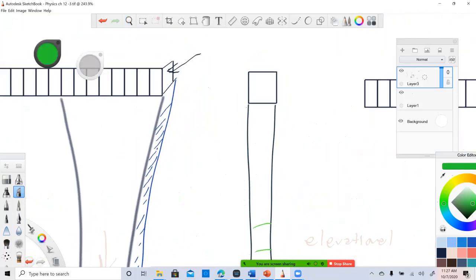and remember, this is just one element in a line of elements, but we're looking at it sideways now. Well, why not every element has its own focus. Now, mechanically, with the lens, now we're mechanically focusing in that other resolution, that elevational resolution.